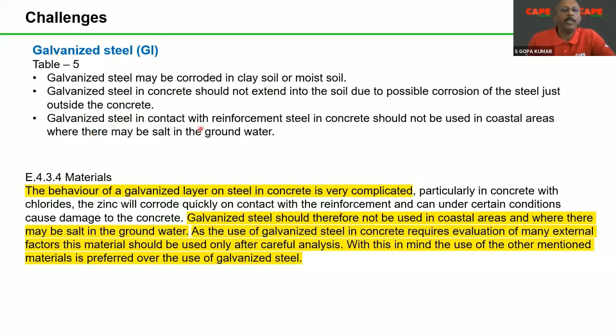So these recommendations are made. The last one: galvanized steel in contact with reinforcement steel in concrete should not be used in coastal areas, because if you put GI inside the concrete, it will corrode faster. So GI cannot be used in soil because of corrosion. GI cannot be used in coastal areas or in places where you have salt water. You will be in trouble. And these comments you are supposed to read and understand.